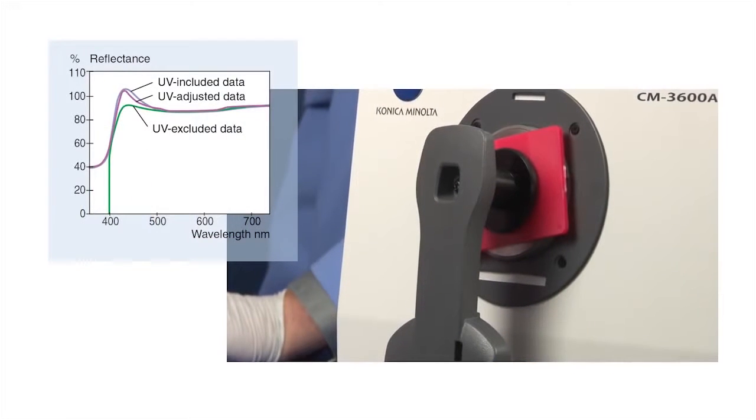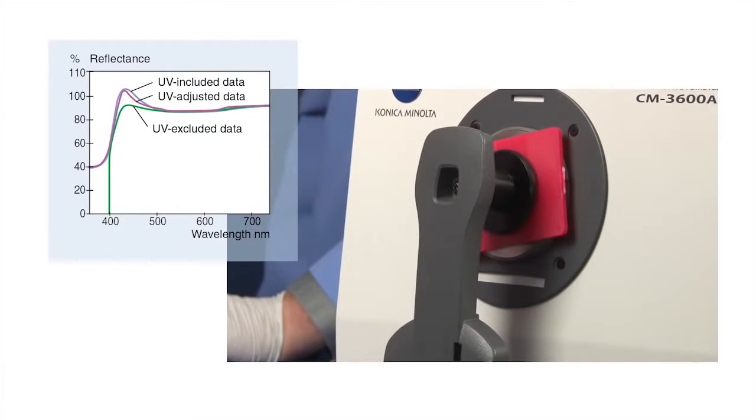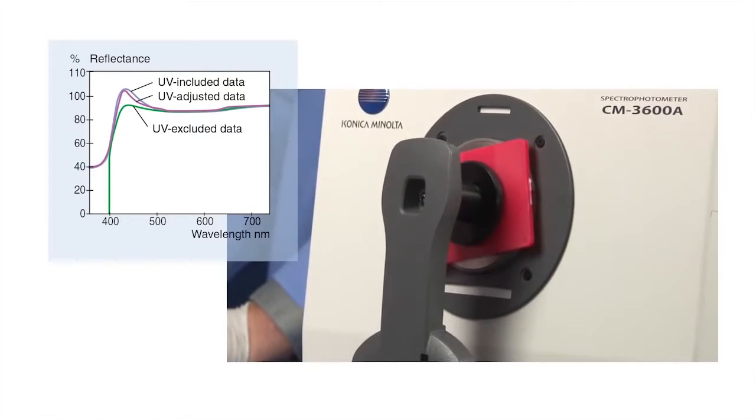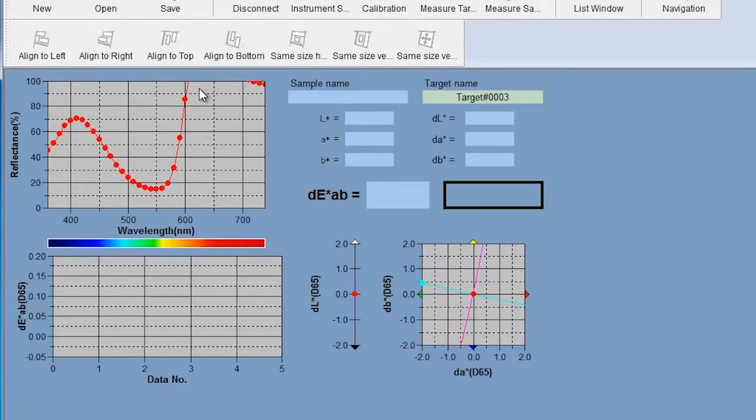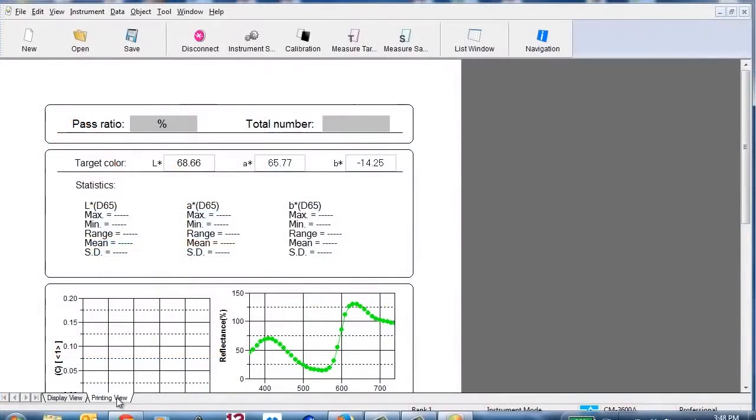The patented numerical UV control method, used by the CM3600A, provides precise control by using proprietary calculations to combine the results from flashes of two xenon lamps.